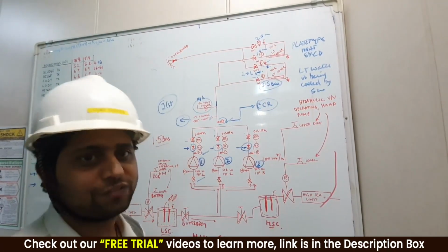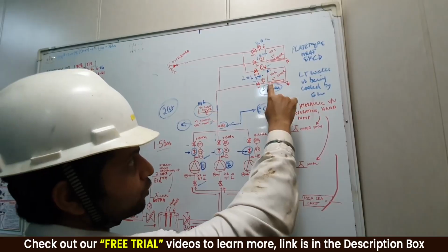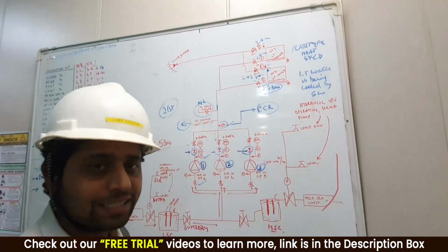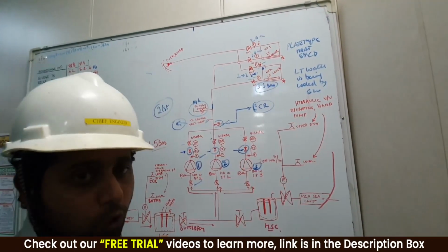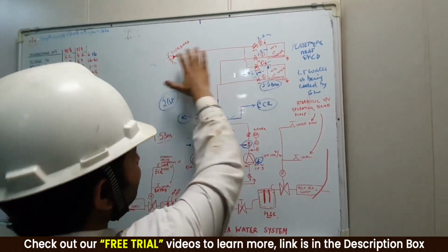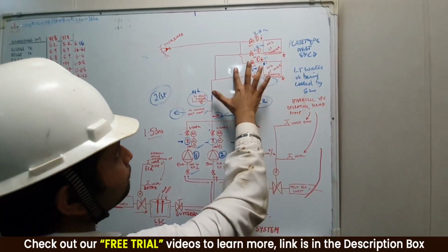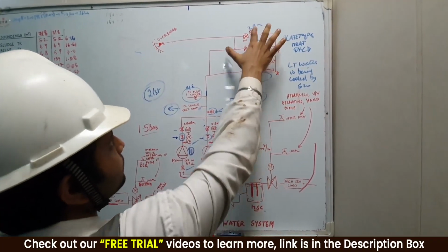So it depends where the filter is fitted, guys. What is important is where the pressure gauge is fitted, before the filter or after the filter. That decides the condition of the filter. Always very important for you to remember, guys. Copy it, guys? And then it goes overboard. So this is, guys, how you need to understand in a simple way how a main seawater system works.